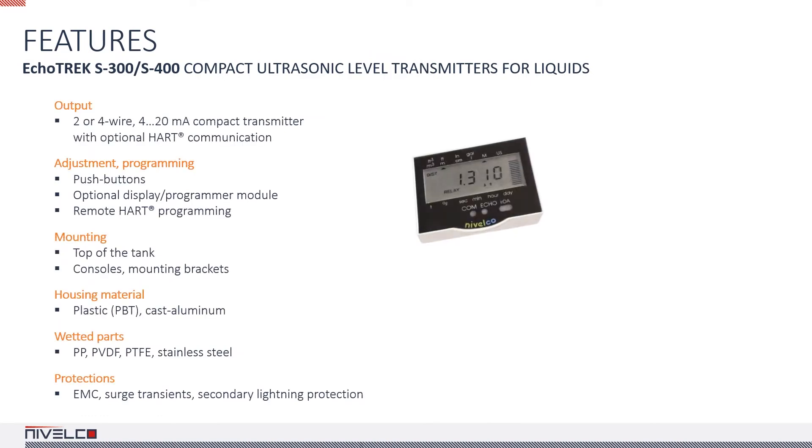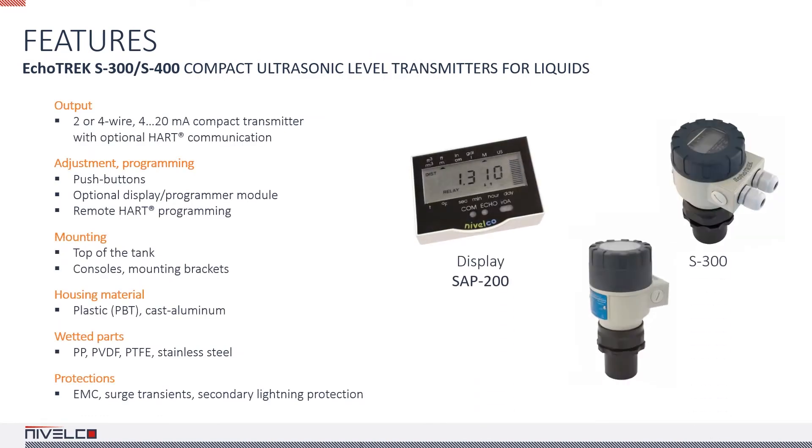Let's talk about transmitters for liquids. The EchoTREK is a 2 or 4-wire, 4 to 20 mA compact device with optional HART communication. The device can be mounted on the top of the tank using a process connection or a mounting bracket. The transmitters can be purchased with a plastic or powder-coated aluminum housing. The material of the wetted parts can be PP, PVDF, PTFE, or stainless steel. The chosen material needs to be chemically compatible with the substances involved in the application.